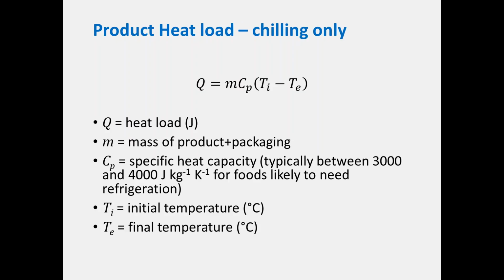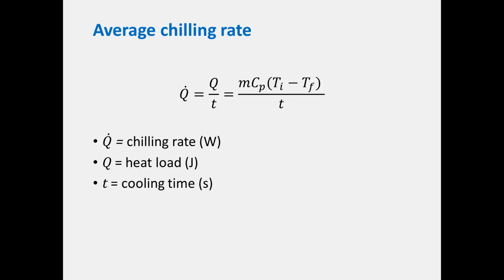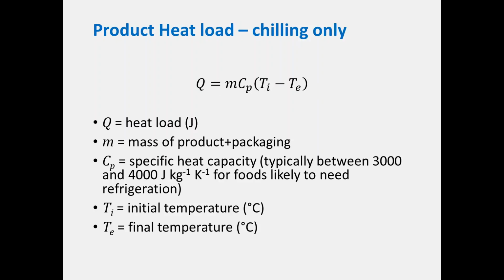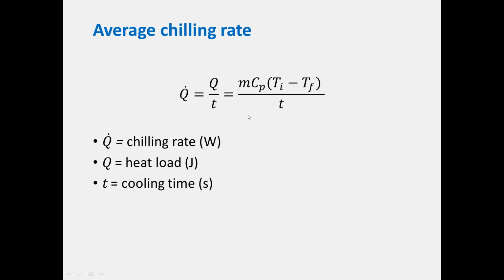So you use 4,000 joules per kilogram Kelvin - that's why I'm using joules rather than kilojoules. Say you have 1,000 kilos: multiply by 4,000, and if your initial temperature is 22 degrees and your target temperature is 1 degree, it'd be 1,000 kilos times 4,000 times 21, giving you your heat load in joules. Then you divide by the time required in seconds, which gives you your average chilling rate.